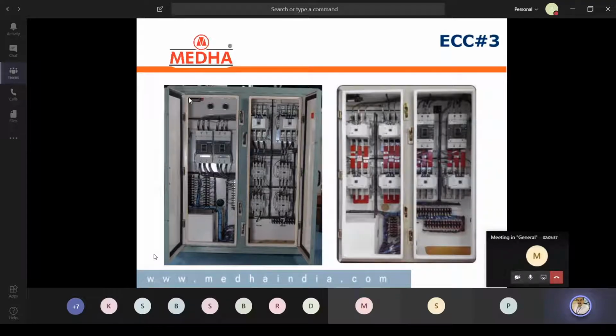And internally there is one sensor, a pressure sensor. This is MRPR, main reservoir pressure sensor, for controlling the compression. Okay, and here for 2 radiator fans, 2 parallel paths are available, 1 breaker MCCB and 3 contactors. So here contactors are also for 2 modes, slow speed and fast speed. So always these 2 breakers MCCB should be kept manually in on position. Their breaker feedback we are also monitoring as a digital input, and in case of tripped or off position, the system will declare a fault: so and so breaker is off, radiator fan blower 1 or 2 in off position. So always manually we have to keep these 2 in on position.